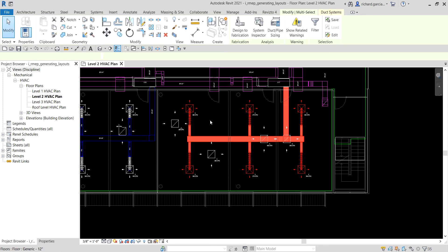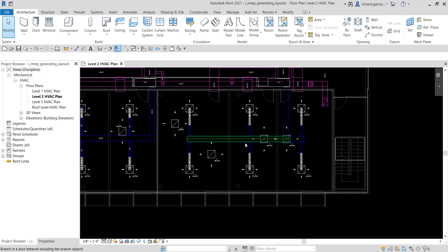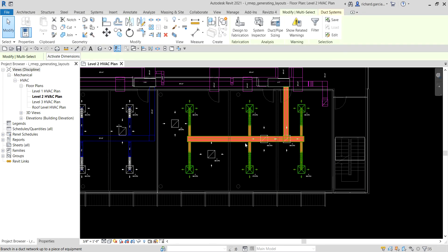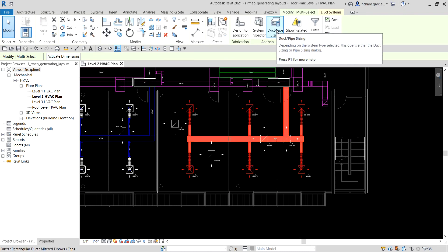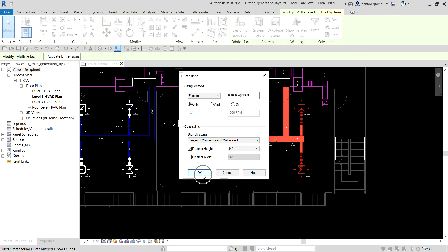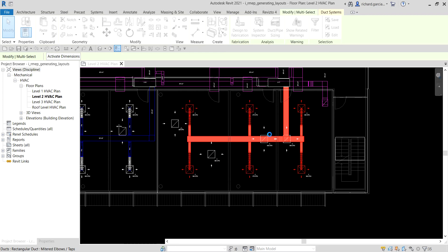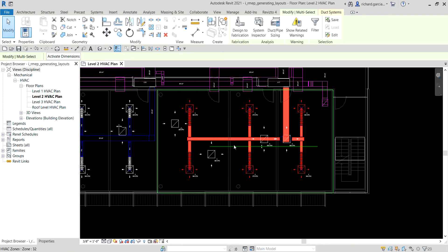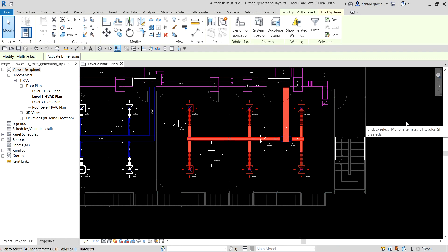Let me quickly show you again: hover your pointer, press Tab twice until the network highlights, then click, and select Pipe Sizing. I'm going to use Friction Only with the default settings, and for the restriction I'll restrict the height to 14 inches — larger of connector and calculated. I'll select OK, and Revit will now automatically size your duct. There you go — click outside to deselect.